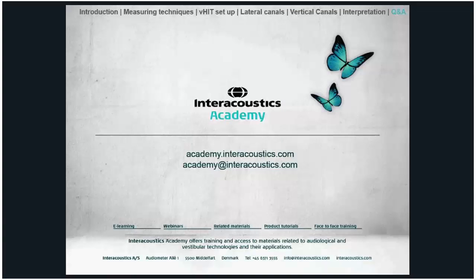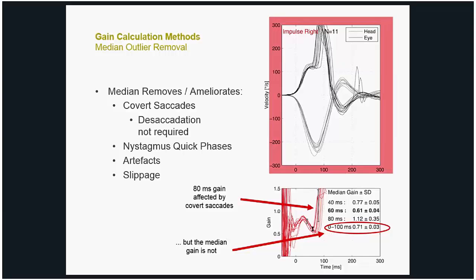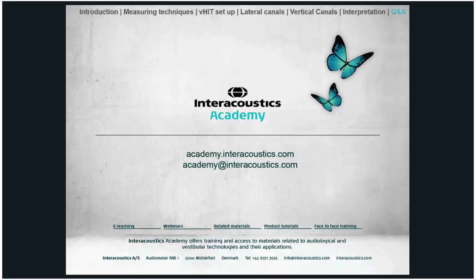Joachim asked: how will it affect the results of vertical impulses if head movement is more translational rather than rotational? Translational head movement will not have an effect on the angular VOR. However, translational movement can have an effect on slippage — if the camera is not tightly enough fixed to the head you will get slippage effects from the translation. But it will not affect the angular VOR itself, so with an ideal system it shouldn't have any effect.